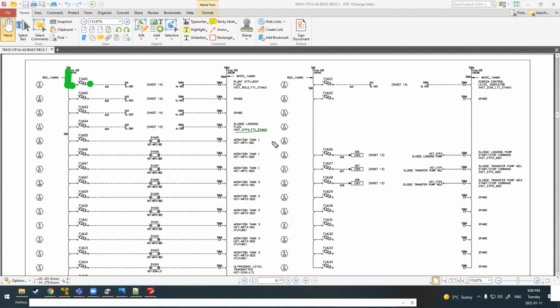I can tell you that that's actually Hagersville sewage treatment. STP is sludge transfer pump 3. FT1 is flow transmitter. And STAAI is, I believe, status analog input. That is just an example. There is no universal standard for tagging. Just sometimes you will have very nice drawings that will have that. This for Logix 5000 will show up in the processor.